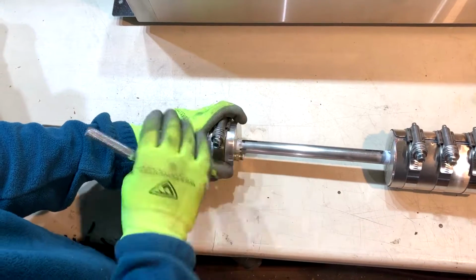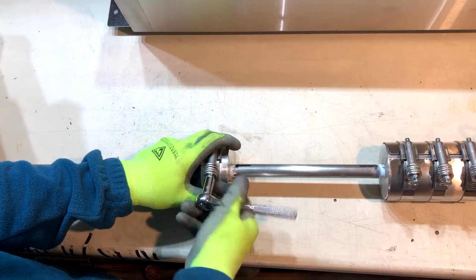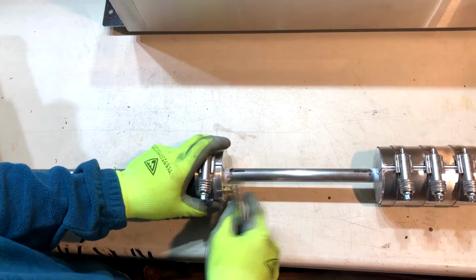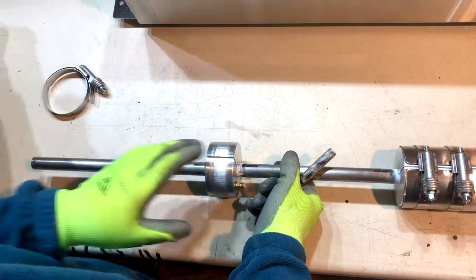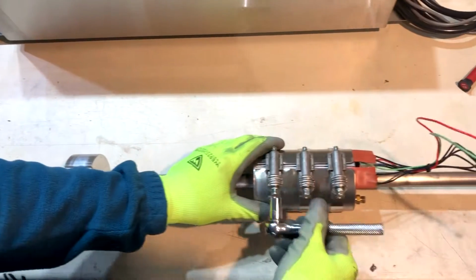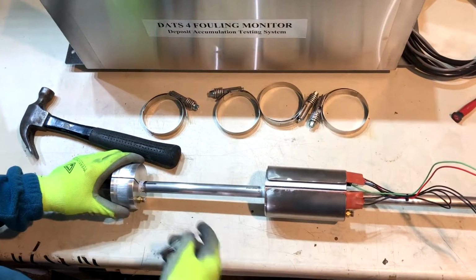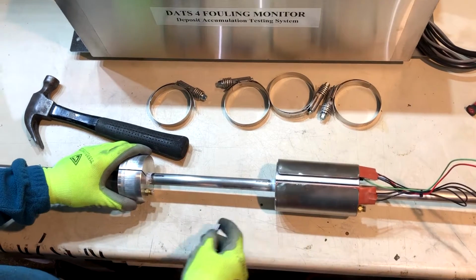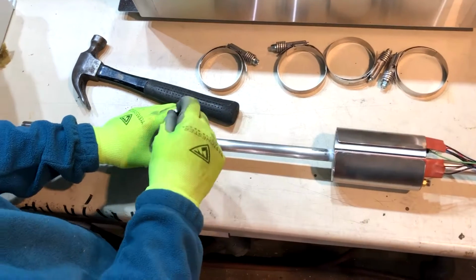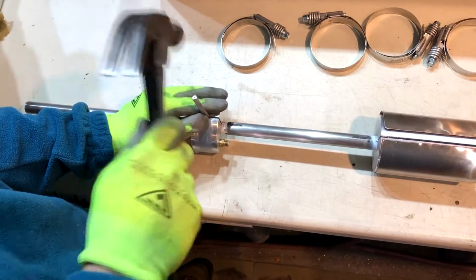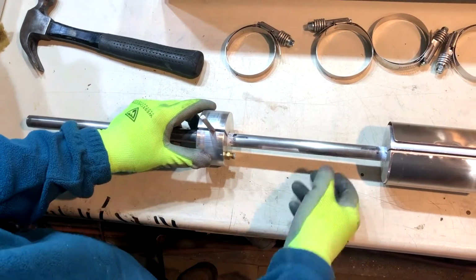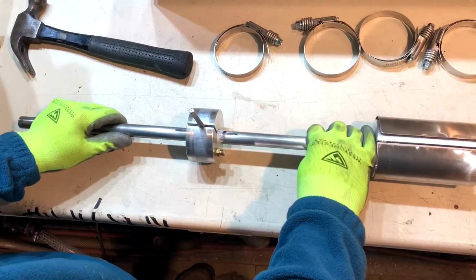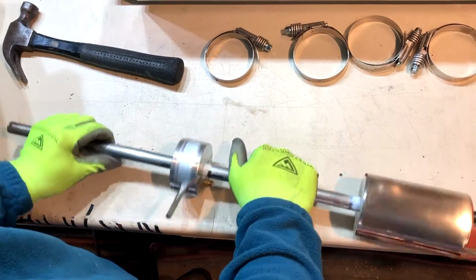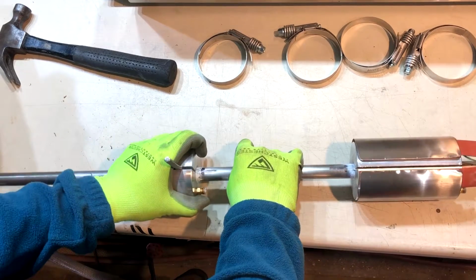Okay, so with the heat exchanger core out, we have our ratchet wrench and the 4 clamps to remove. We'll loosen them first, pulling the clamps off. You'll notice they have the Belleville springs on there. You don't have to be worried about the torque right now. We'll remove the rest of these off of here. Okay, so with the clamps removed from the block, the inlet block and the heater block, we take our wedge and hammer and drive this gently into the tube.